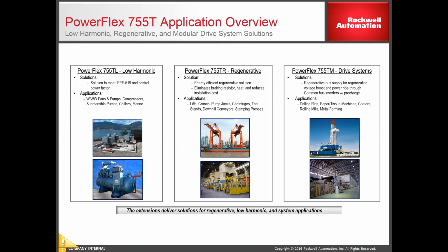So again, different applications for the low harmonics. I mean, for water, wastewater type applications, that's always an issue, being able to meet IEEE 519, fans and pumps. For the regenerative drive, lifts, cranes, pump jacks, and then the TM drive, the system level drive, or the common bus drive, paper machines, drill rigs, rolling mills, metal forming. I mean, there's a host of applications we can now reach that we couldn't reach before with this new drive that's coming out.